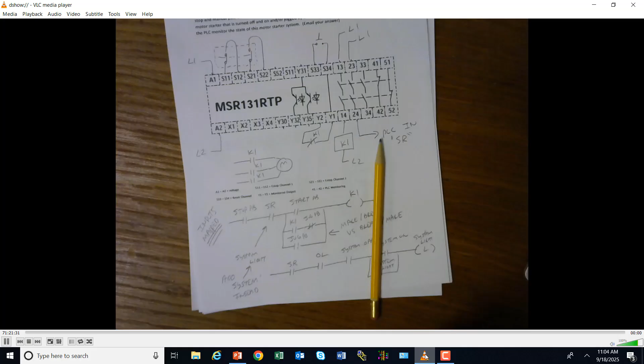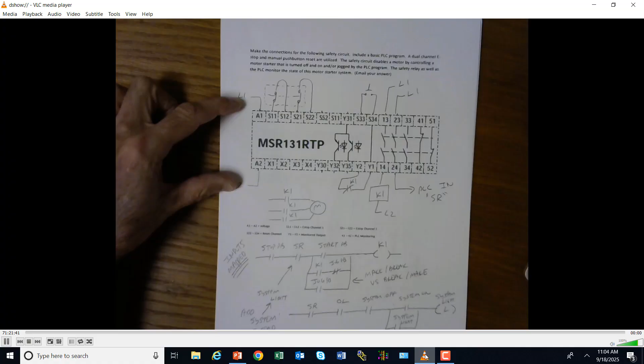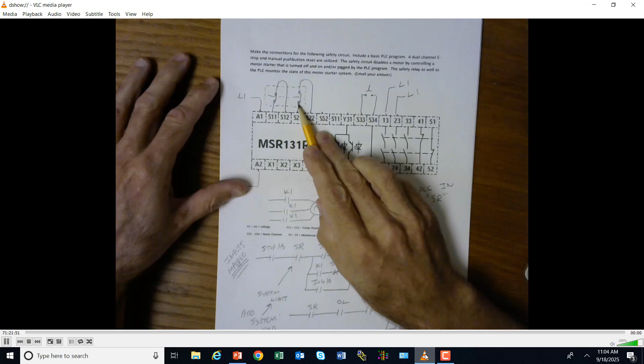Quiz review. So that was the safety relay setup. We did a little bit of this. Everybody's doing pretty good on this. Just want to reiterate one time the safety relay here. I just got line 1, line 2, whether it's an AC or a DC relay. It's got a dual channel E-stop here. It could have multiple other E-stops or safety circuits or safety gates, but it just said do an E-stop, and I've got the dotted line around there to indicate it.